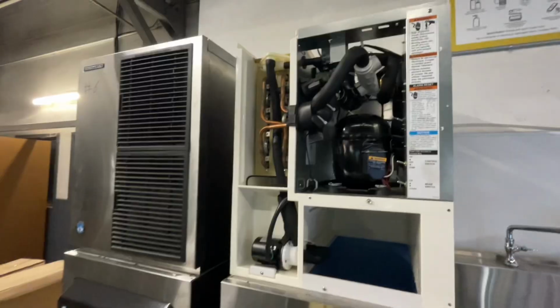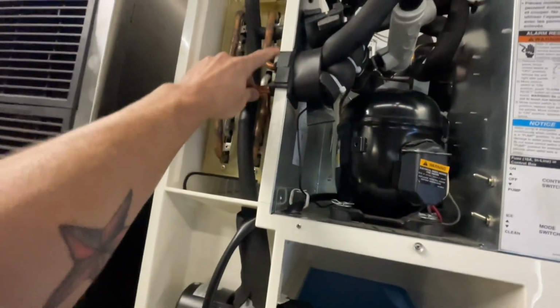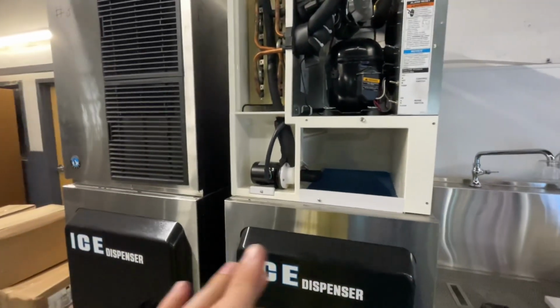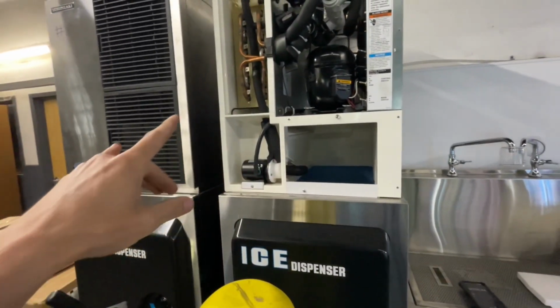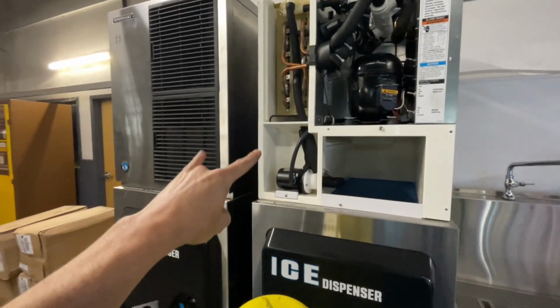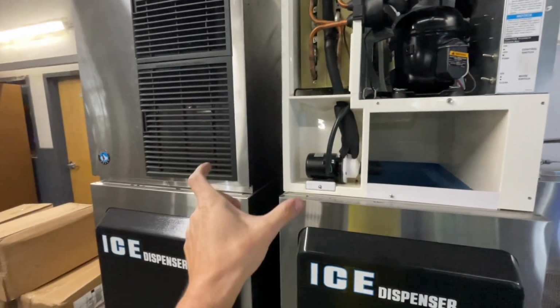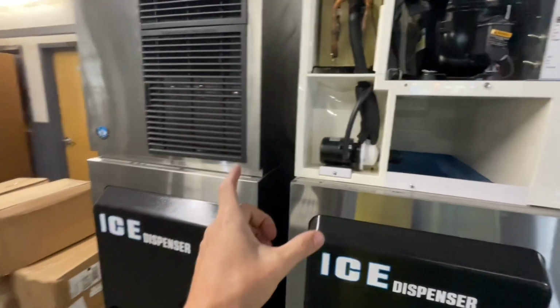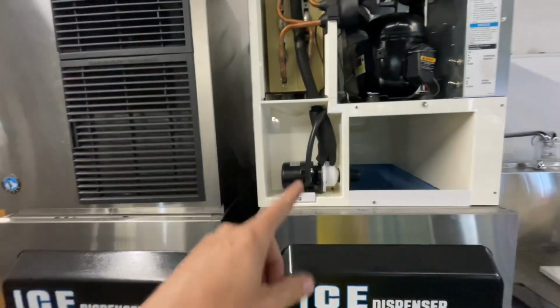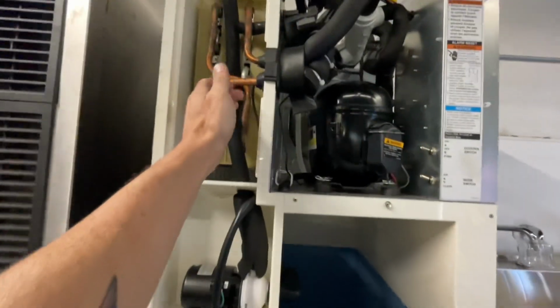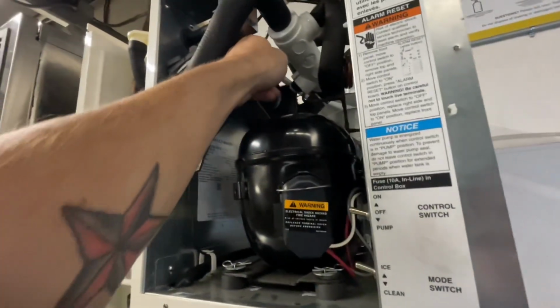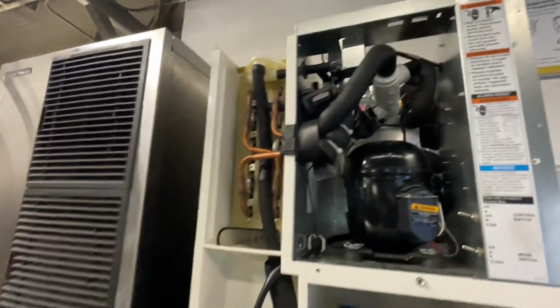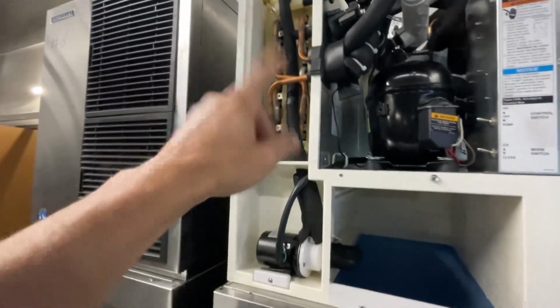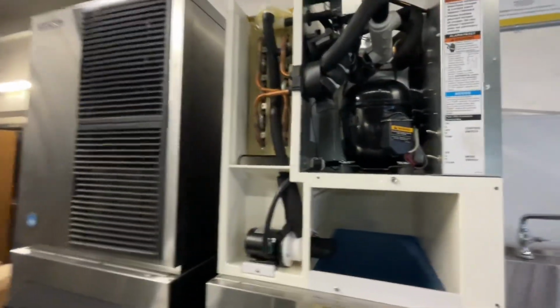That's just me guessing. Almost 6 minutes later, we're done harvesting. I'm thinking, possibly, if both these machines here are working off the same water filter, and if they're both in harvest at the same time, and it's at night and cold in this warehouse, the chances are this thing would reach 20 minutes without harvesting, or without the thermistor reaching 48 degrees, because it froze up, and then it was cold, and it wasn't getting water. We're just going to go ahead and swap out the water filter, and everything will probably be all right.